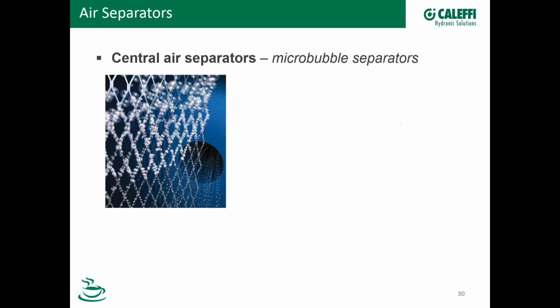Right. So central air separators have a coalescing element that captures microbubbles. Here's a graphic that illustrates that. As the flow comes in through that pipe, you can see at the bottom these are really small bubbles. Those little bubbles will cling to the sharp edges of a coalescing element, and the bubbles will join together and rise up as their buoyancy increases and eventually become large enough bubbles that they'll go up to the top, and then they'll build up in the top of the air vent and be expelled out of the system. So again, the key is this coalescing element down here.